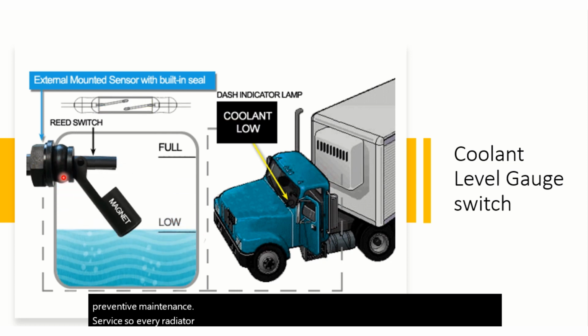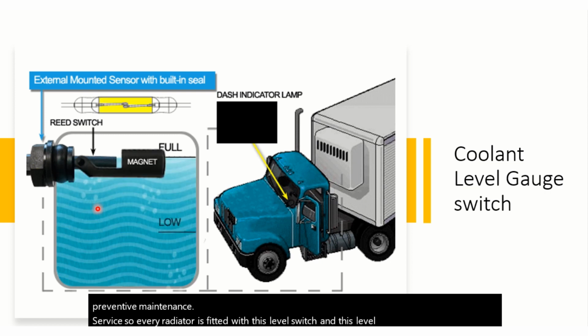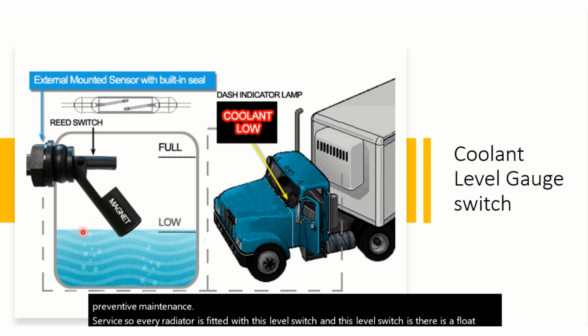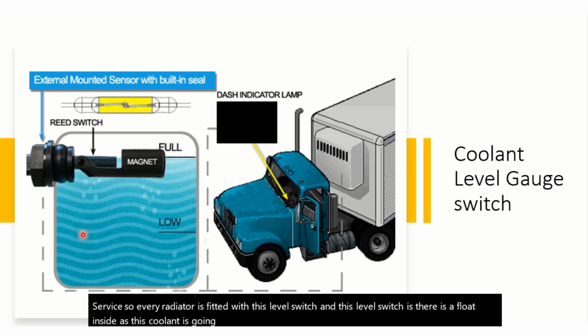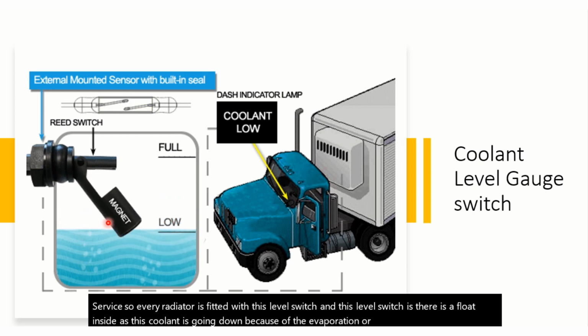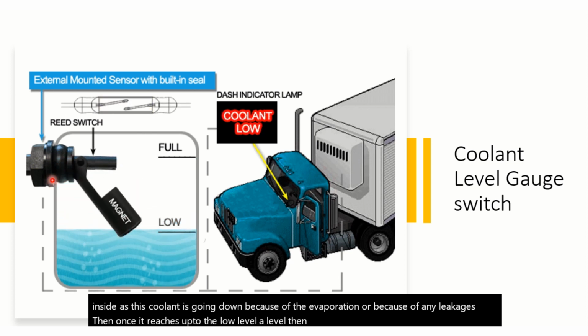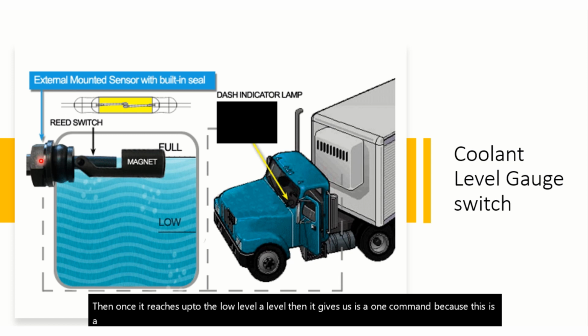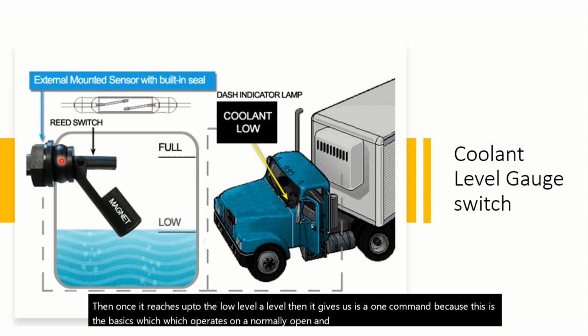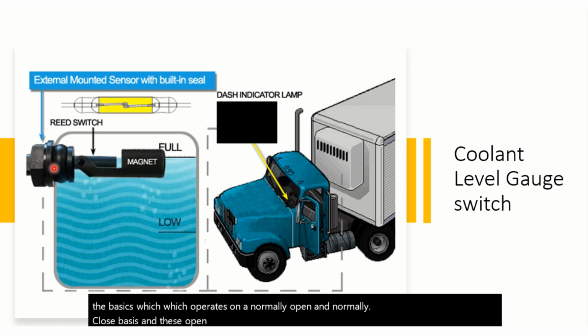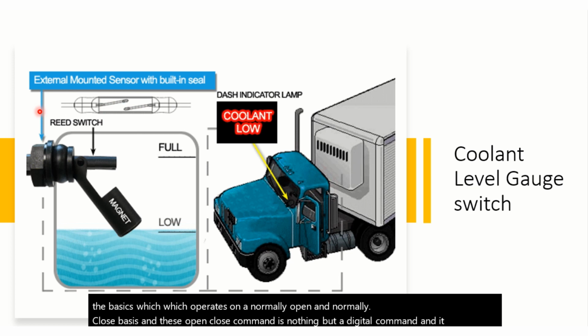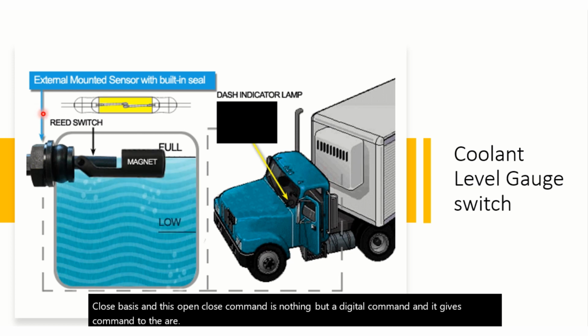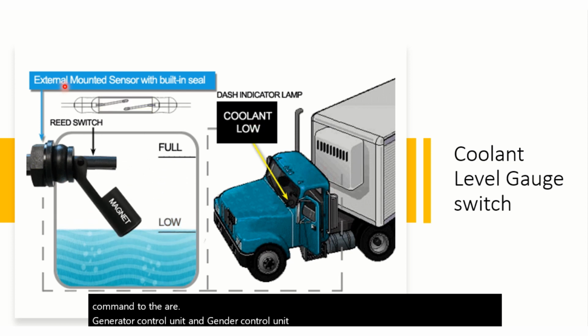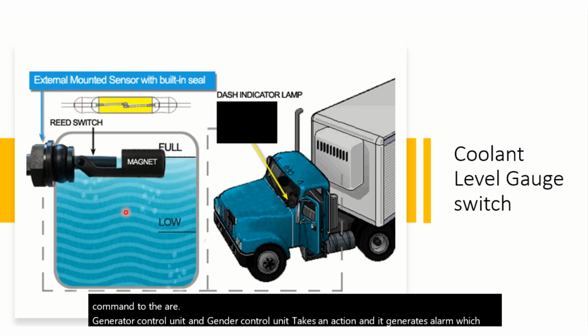Every radiator is fitted with this level switch, and inside this level switch there is a float. As the coolant goes down because of evaporation or any leakages and reaches the low level, it gives us one command, because this is a basic switch which operates on a normally open and normally closed basis, and this open-close command is nothing but a digital command. It gives a command to our generator control unit, and the generator control unit takes an action and generates an alarm which travels through RS485 to our central knob.